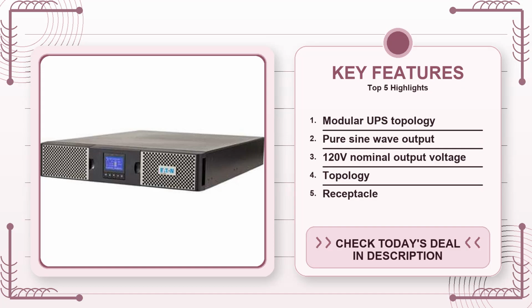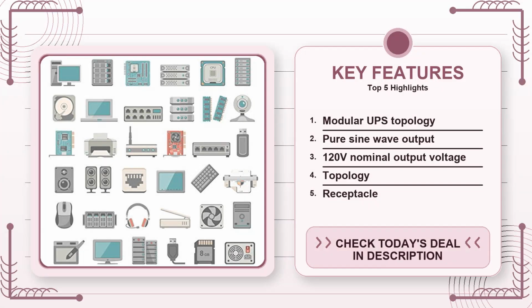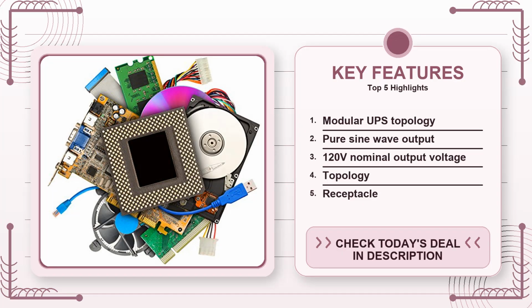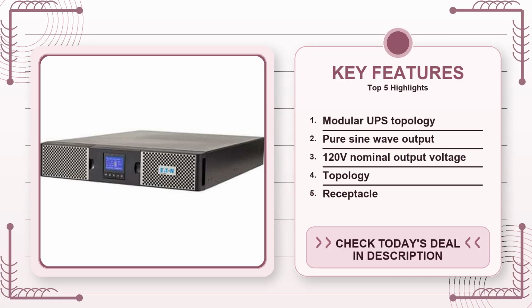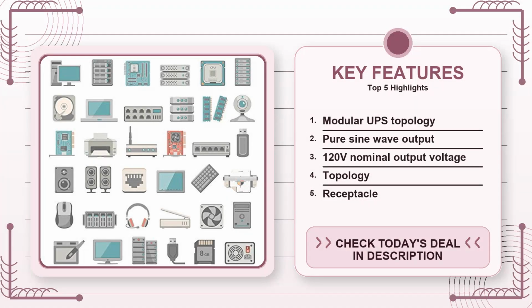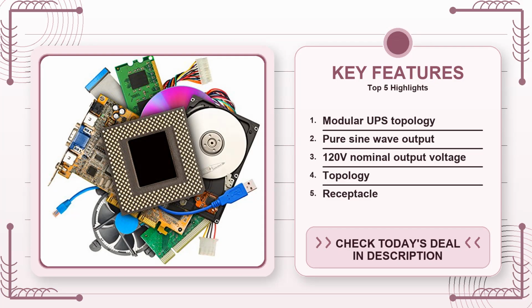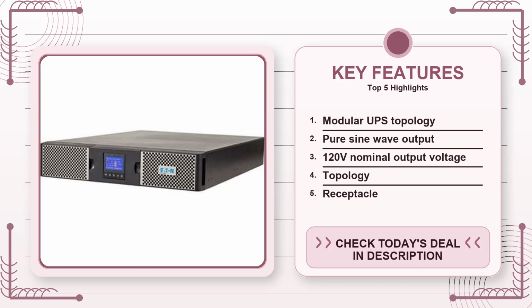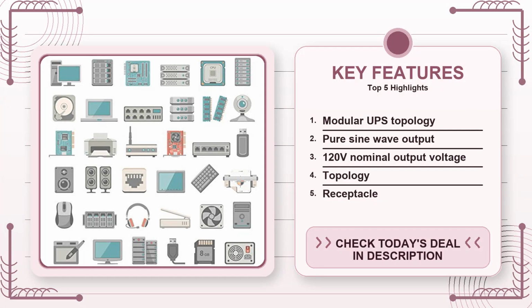The EATON 9PX3000RT sits in the middle of the market, big enough to handle roughly 2.3 kilowatts of equipment, but compact enough to fit into a standard 42U rack without hogging precious space. If you're a freelancer with a single workstation and a monitor, that amount of capacity is overkill. A 600 to 800VA unit would be more cost-effective. On the flip side, if you're running a small server farm with higher draw, you might need a 5 kVA model or a parallel configuration, because the 3000VA will start to struggle once you push past 2.5 kW for longer than a few minutes.